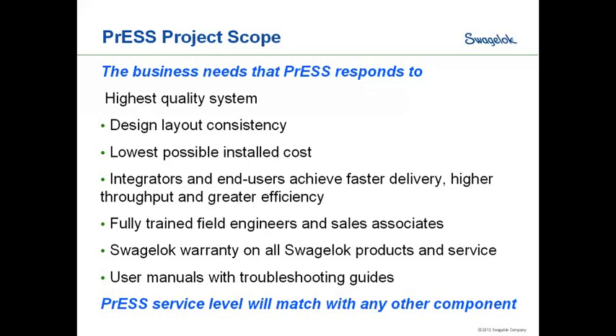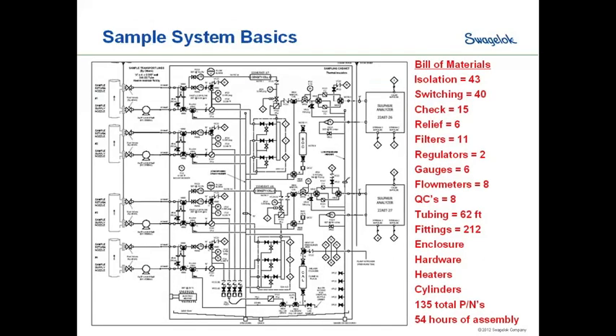The PRESS service level is designed to feel like any other component offered by Swagelok. In the past, and still many times today, these systems are engineered using discrete components following a P&ID layout, where each discrete component is placed and connected to the next. This can be very time consuming and difficult to do correctly. A typical example — a four-process-stream system with two analyzers — can easily have 43 isolation valves, 40 switching valves, and 135 separate individual part numbers.